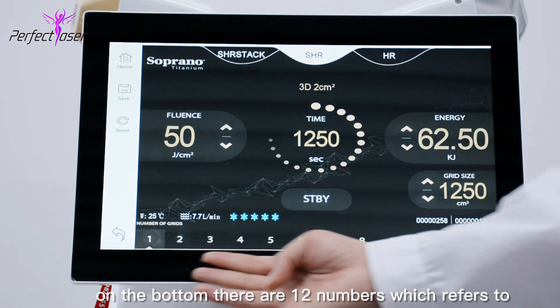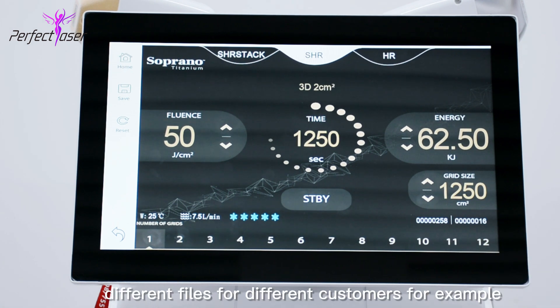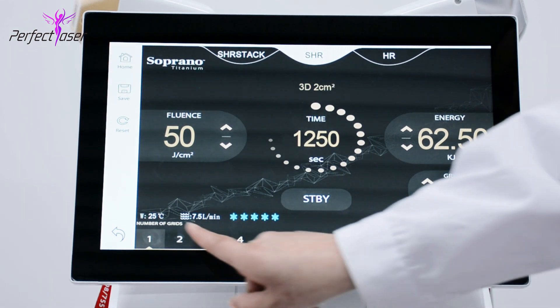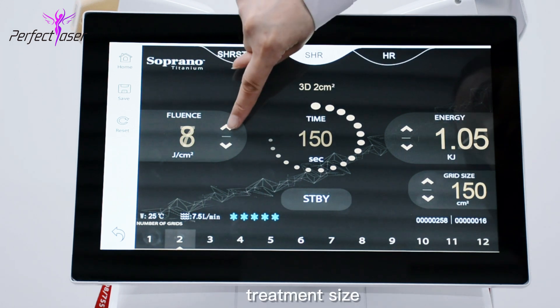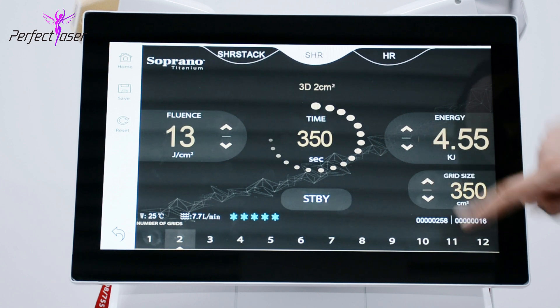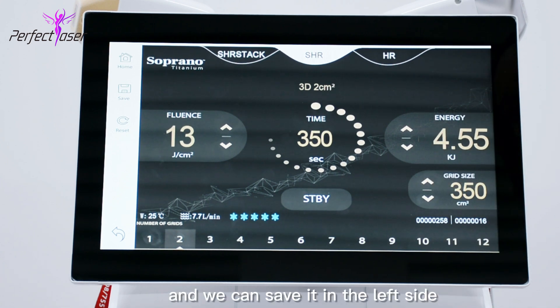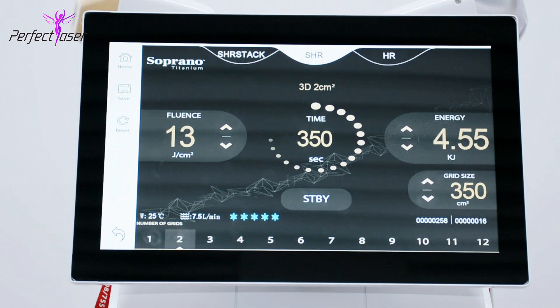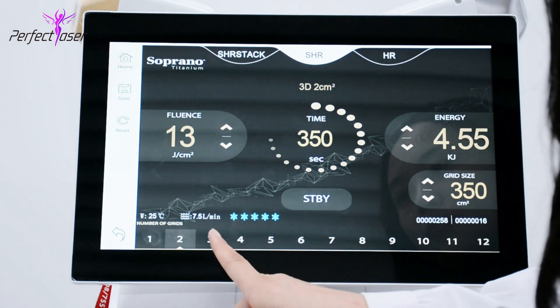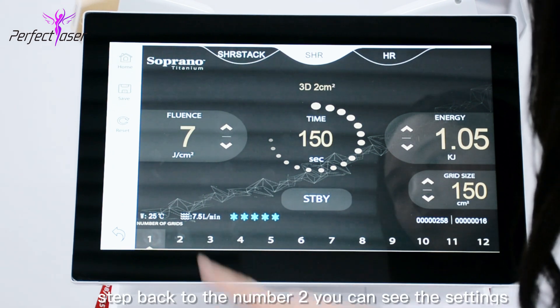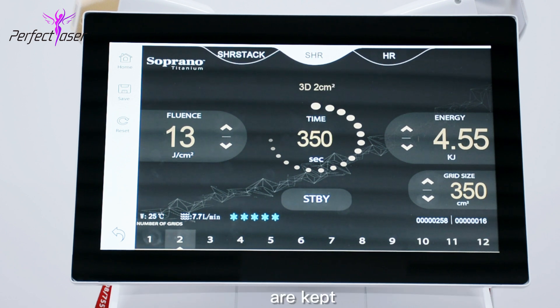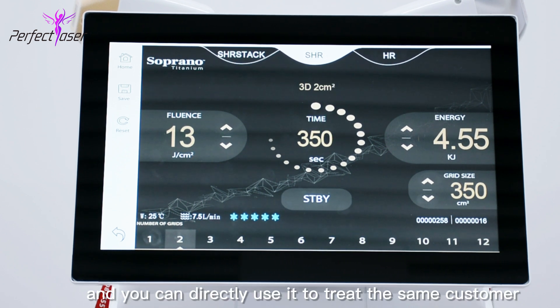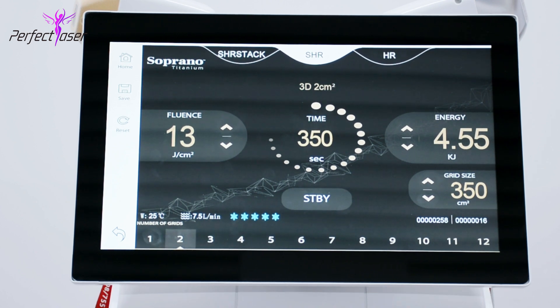At the bottom there are 12 numbers which refer to different files for different customers. For example, you can adjust the energy and the treatment size, then save the settings on the left side and they are kept in the machine. Next time you return to that number slot, the settings are recalled and you can directly use them to treat the same customer.